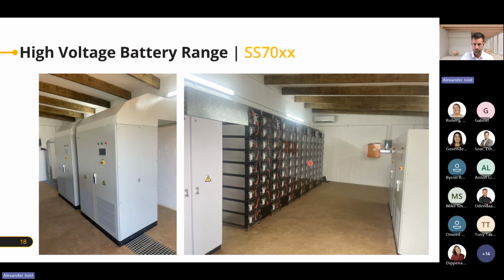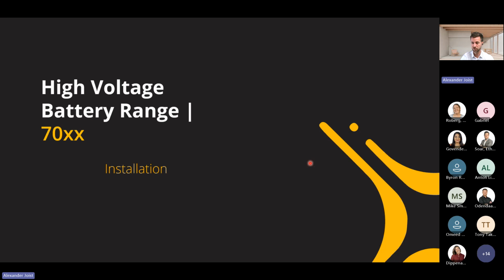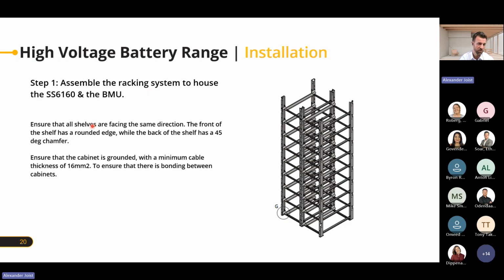Okay, I'll continue. If we look at quick installation information on the batteries: the very first thing to do is assembly of the rack system to house the SS6160 and the BMU. You're going to build up the racking system, and it's very easy, not too difficult. There's also more information on exactly how to do it. Important is that you also always do the grounding of the rack — it's a metal part, but the battery in general also needs to be grounded. So always make sure at the bottom you ground it. That's just a little marker for the installation of the racking system.